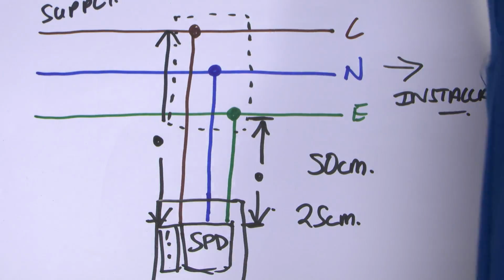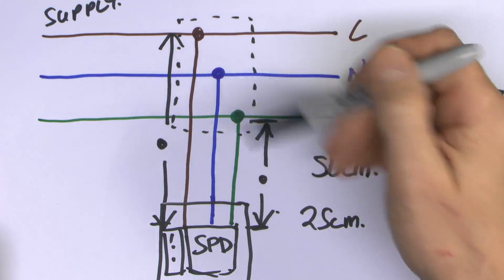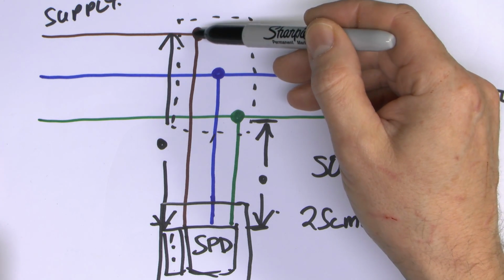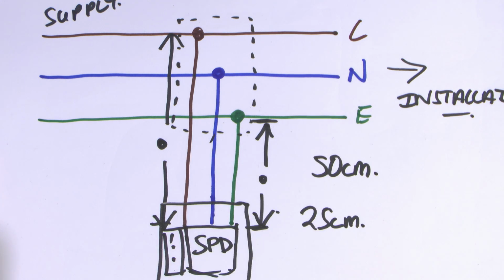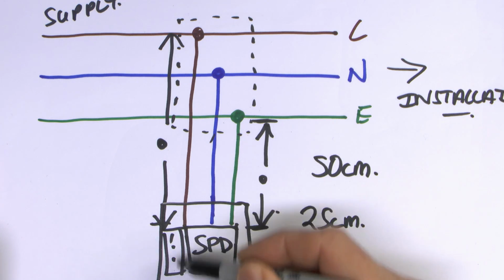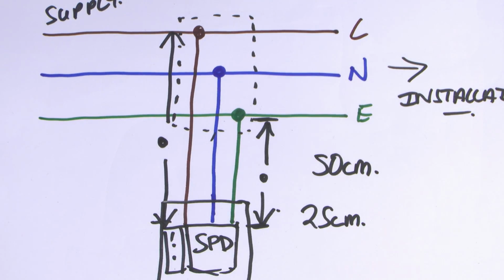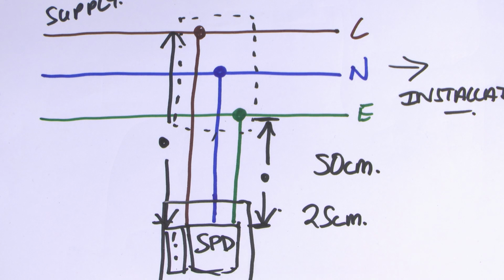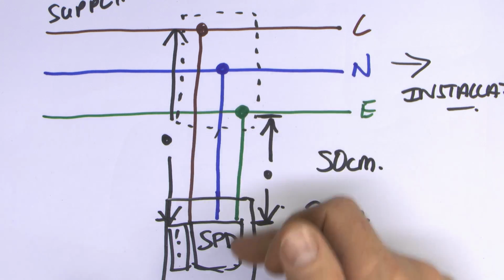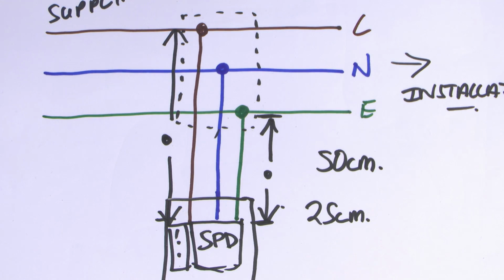And let's face it, here's the wiring regulations book. This is nearly 30 centimetres across, so that's really no distance at all. And it's not just the length between the two pieces of equipment, it's not the length between the casings, it's the actual length of the whole wire. So in this case it would be from the actual point it connects here, all the way through outside the casing, outside there, inside the casing, and then into the terminal. And of course, if this looped underneath and came around the back, that's all adding extra length. So this sort of arrangement, where it's just coming off a stub or a direct tap off of the main line, is a pretty poor choice in terms of installation, because you've got all this extra length here. It's almost inevitable it's going to be longer than the maximum half metre which was suggested.